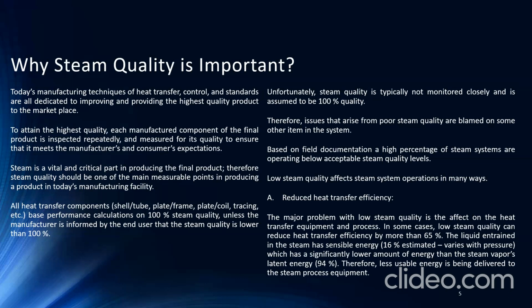A. Reduce heat transfer efficiency. So the major problem with low steam quality is the effect on the heat transfer equipment and process. In some cases, low steam quality can reduce heat transfer efficiency by more than 65%.